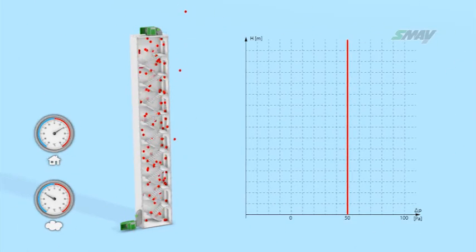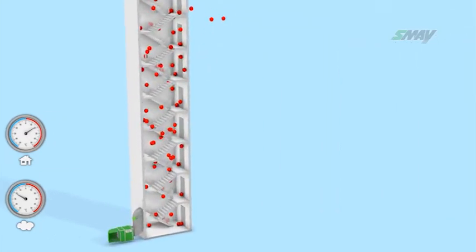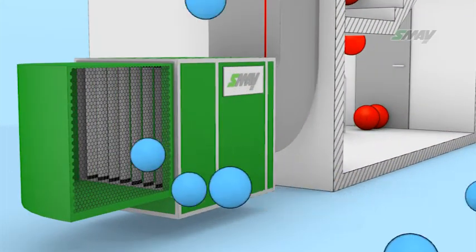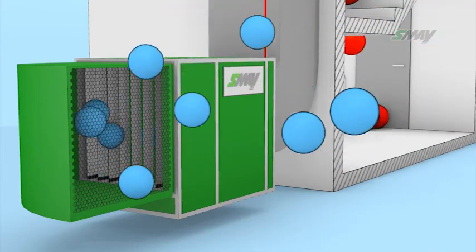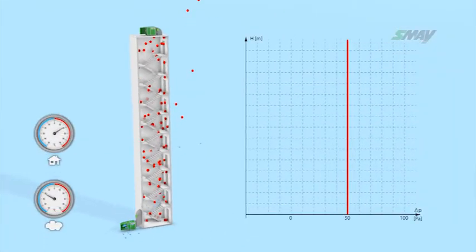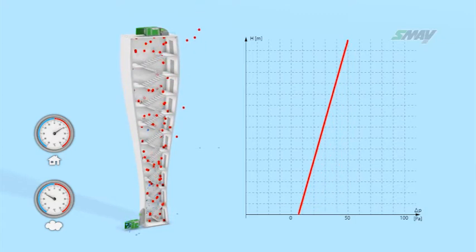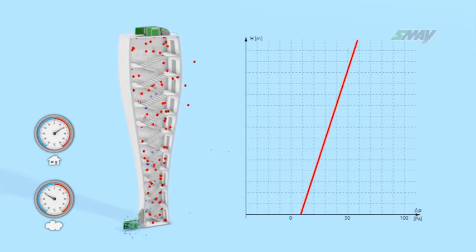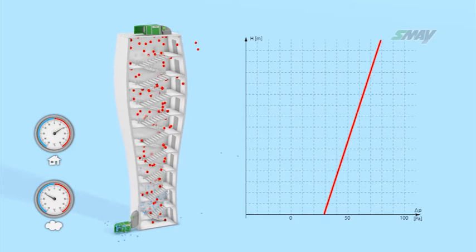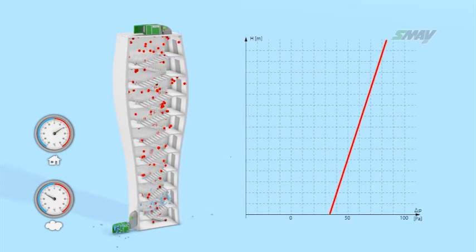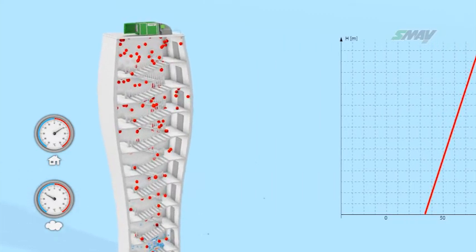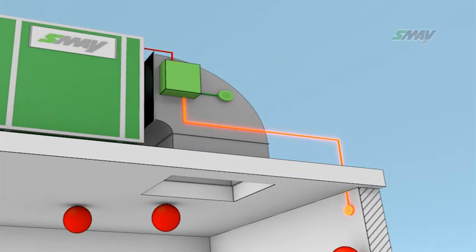If the external air temperature is below the temperature inside the stairwell, the system works similarly — the bottom fan supplies air and the top fan works as an extractor, activating when 50 pascal are exceeded. Supplying the stairwell with external air, the stack effect will occur within its volume, causing temporary negative pressure in the lower sections. The pressure drop causes the bottom fan to supply more and more air, aiming to maintain 50 pascal in the lower section. The excessive pressure increase in the upper part of the stairwell signals the dampers at the upper fan to open, removing the excess air.